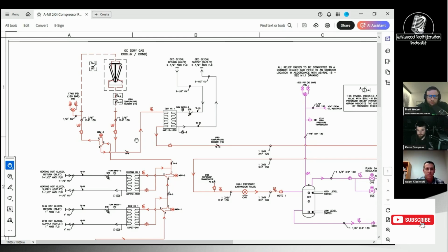I think the best way to control the discharge pressure in cold ambients is fan control. Now, I know we can't always do that, but if we have enough turn down ratio, and if we have stable control of the fans, then the best scenario is to only use the fan control for head pressure control. If we start to have to get into other things, it does add complexities. It does add additional control loops. So it is more challenging.